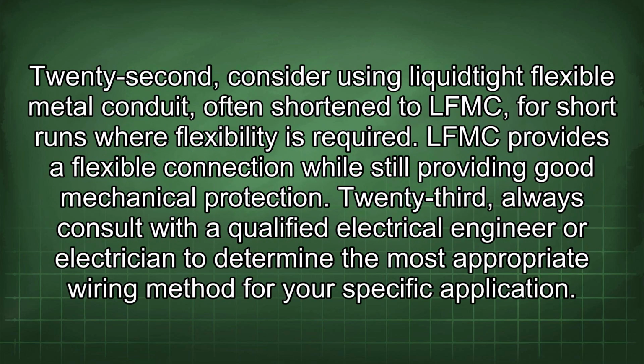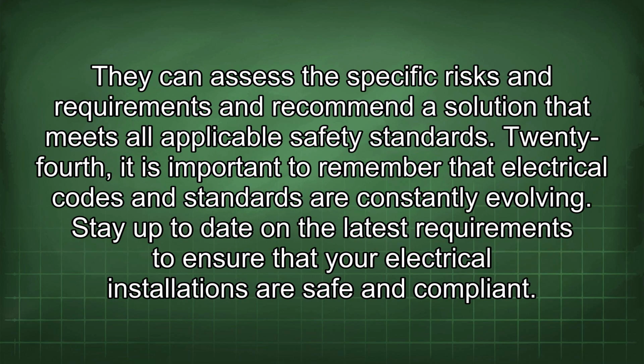22nd, consider using liquid-tight flexible metal conduit, often shortened to LFMC, for short runs where flexibility is required. LFMC provides a flexible connection while still providing good mechanical protection. 23rd, always consult with a qualified electrical engineer or electrician to determine the most appropriate wiring method for your specific application. They can assess the specific risks and requirements and recommend a solution that meets all applicable safety standards.